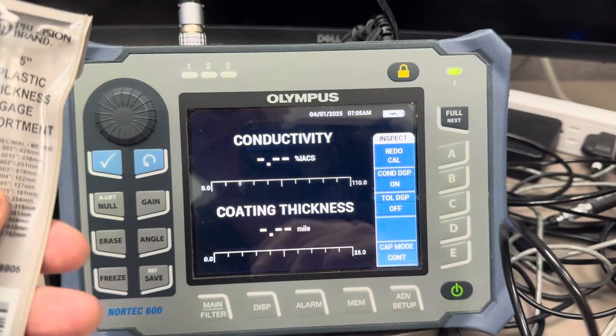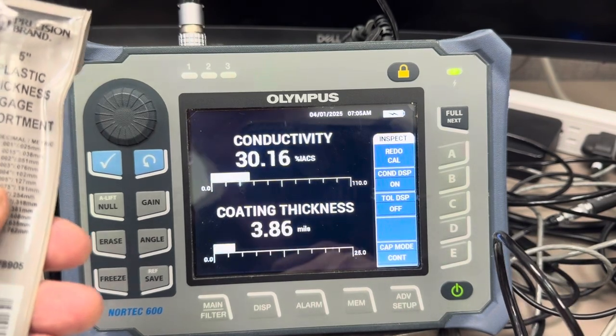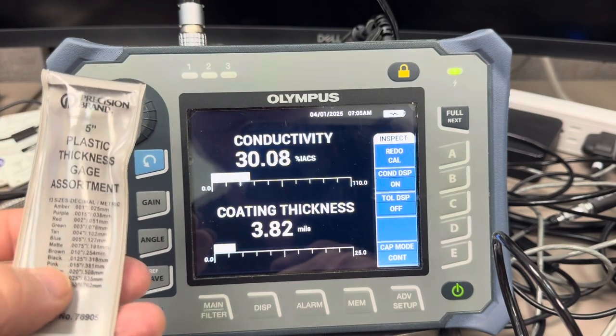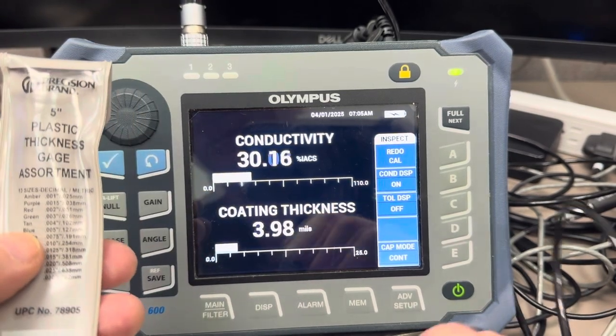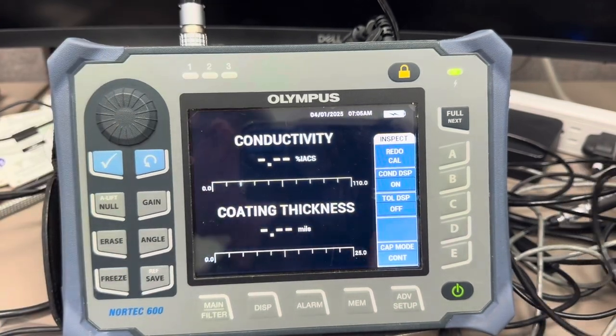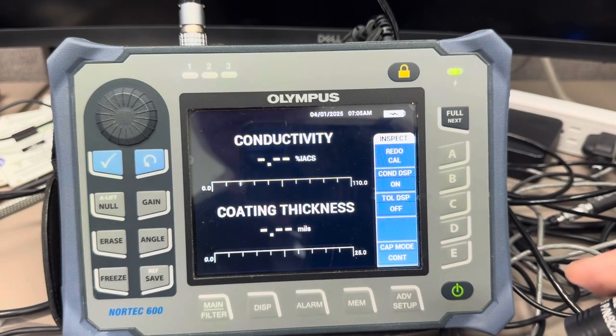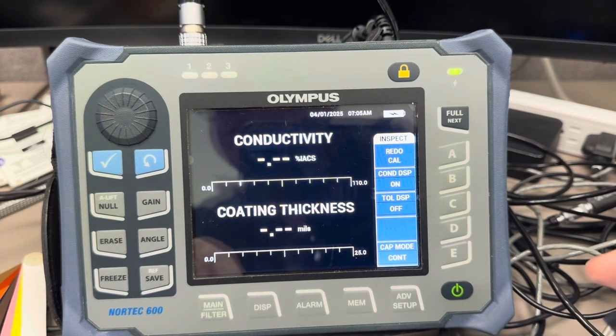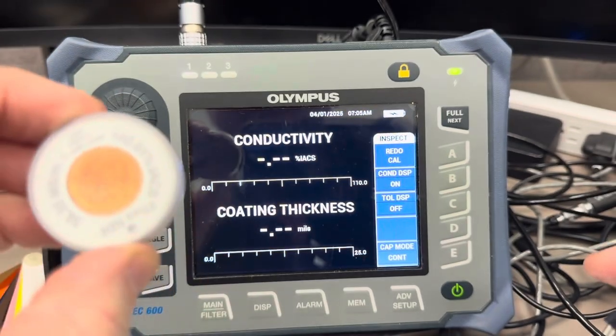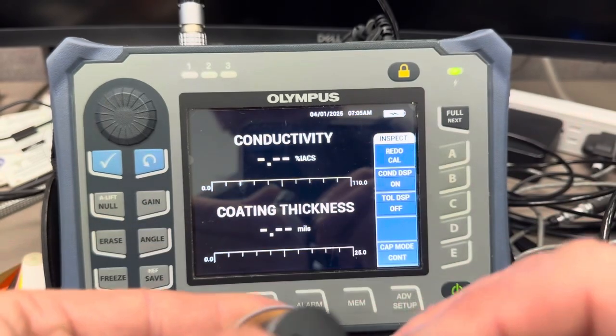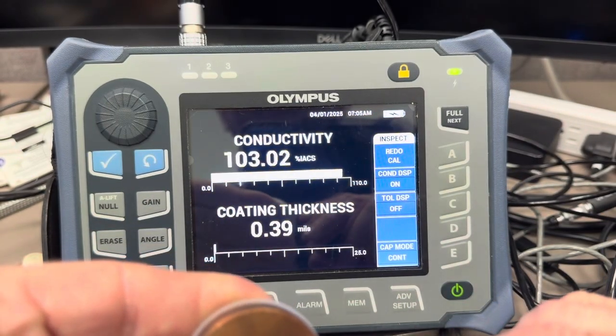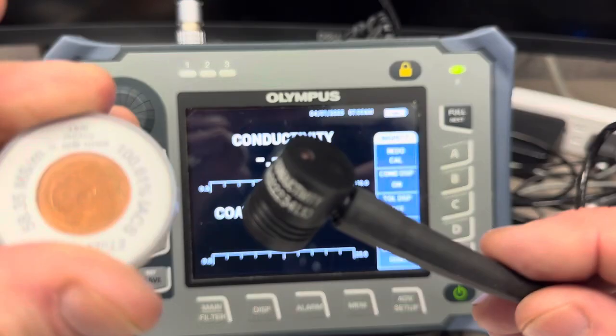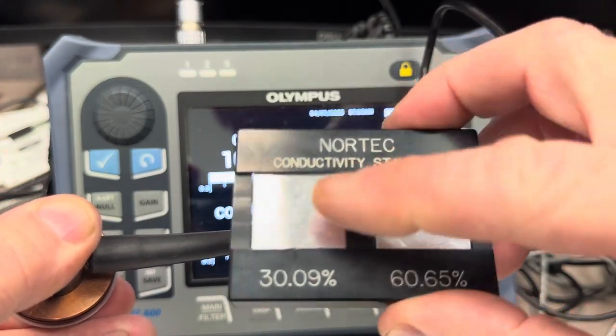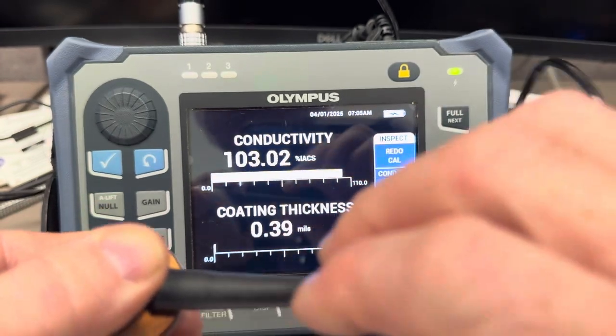Let's go over to the 30.09 and see what we come up with. 30% IACS, just about 4 mils. And again, this shim is 0.004 inches. Excuse me. So now let's try some different materials. This particular sample is copper. It's about 100.6. I'm not going to use any shim. All right, so it says 103%, where it's actually calibrated to 100%. But keep in mind, we calibrated on 30% and 60%, so it's going to be more accurate within these ranges.